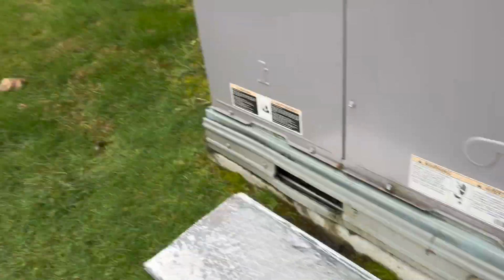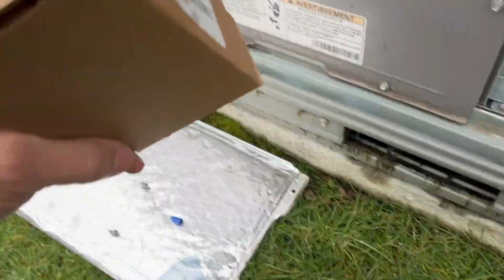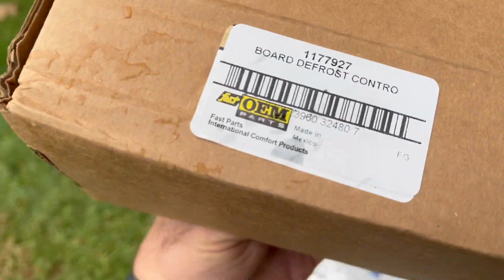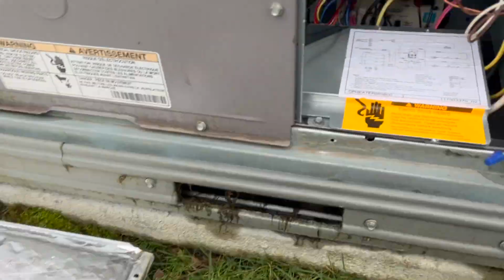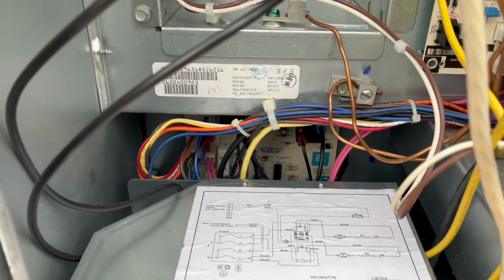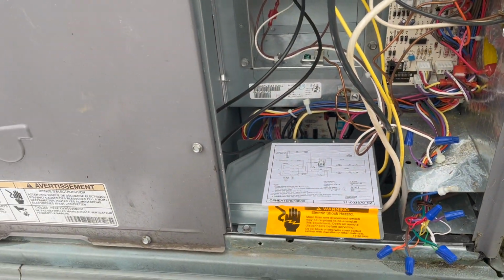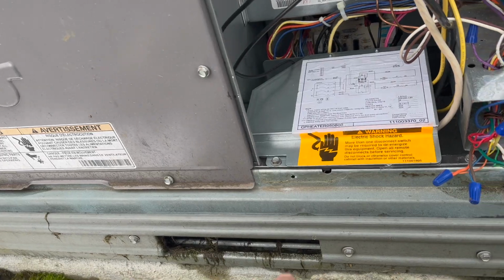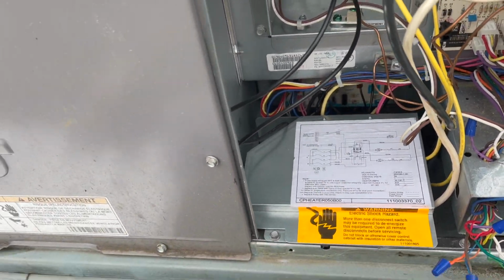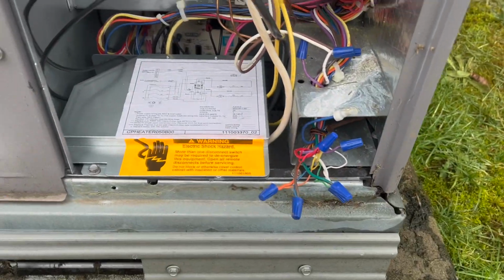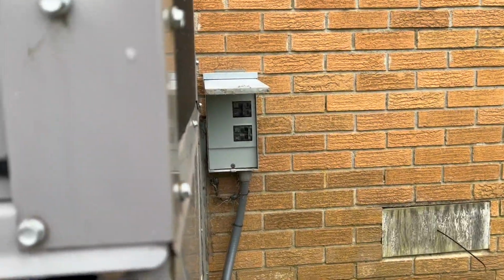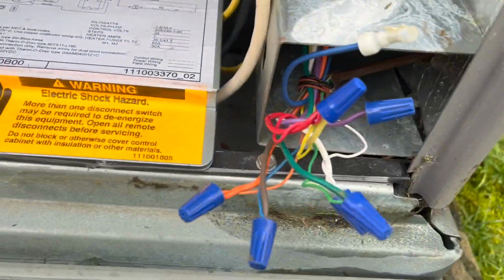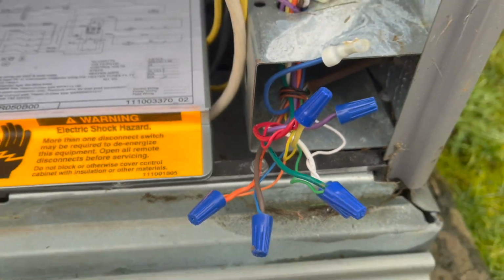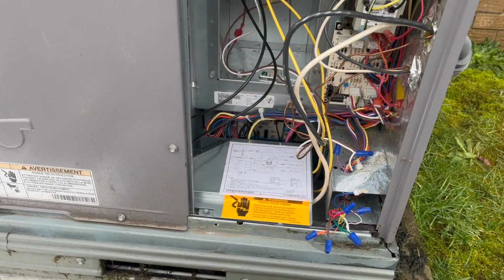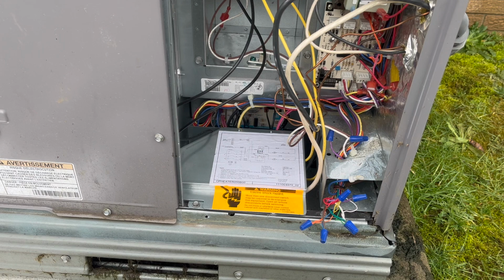Back on site, it's still wet and nasty. Got the defrost control board installed way down there in that little hole. Terrible place to put it, but it is what it is. Have to remove this heat kit area to get back in there. But what I've done is put it in, turned on the unit breaker, and just attached the yellow and red together, because again we have a dead thermostat that I need to go in and take care of.